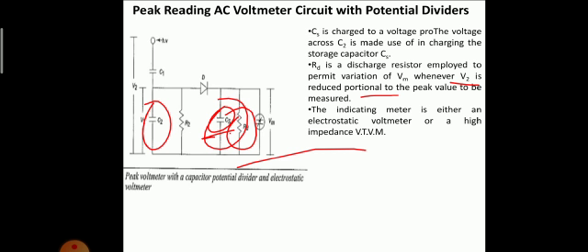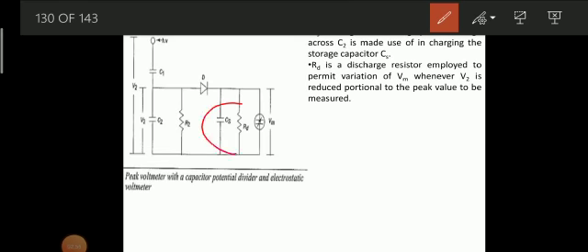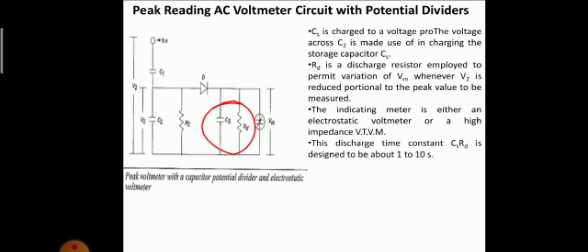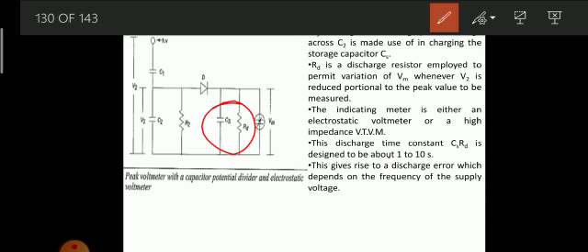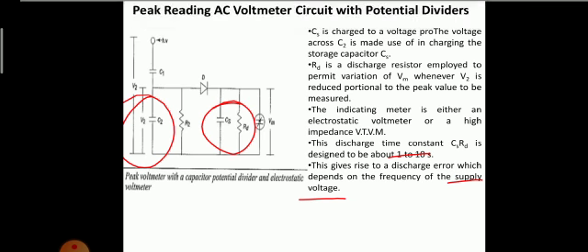The indicating meter is either an electrostatic voltmeter, ESV, which we had seen, or a high impedance vacuum tube voltmeter. The discharge time constant CS into RD is designed to be about 1 to 10 seconds. This gives rise to a discharge error which depends on the frequency of the supply voltage.